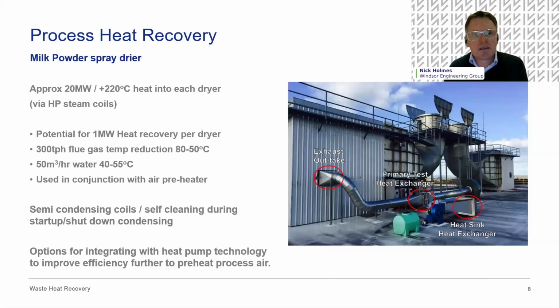A big area we see that there's some real potential in both Australia and New Zealand is in the dairy plants, where they have significantly large thermal energy demands in their spray dryers to turn the milk into powder. Typically, on this project, they use approximately 20 megawatts per dryer of thermal energy. It needs that high temperature to achieve the 220 degrees process air temperature into the dryers. And then the exhaust of that is relatively low. They're exhausting to atmosphere at about 80 degrees, so it's already pretty low grade exhaust temperature.